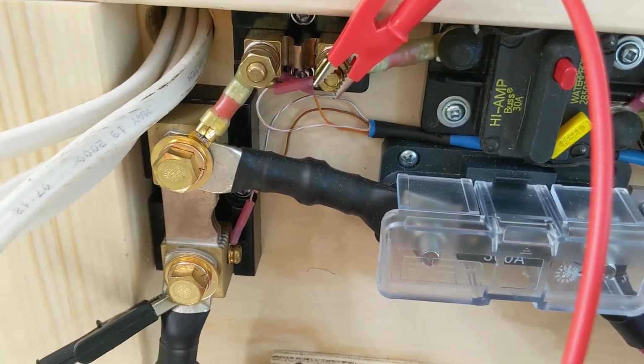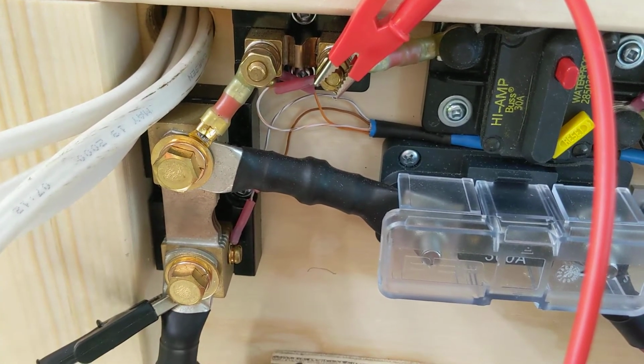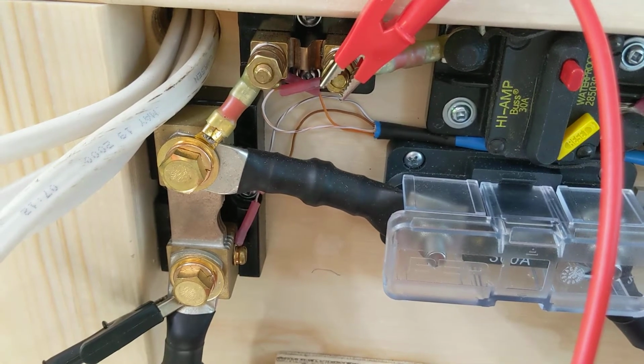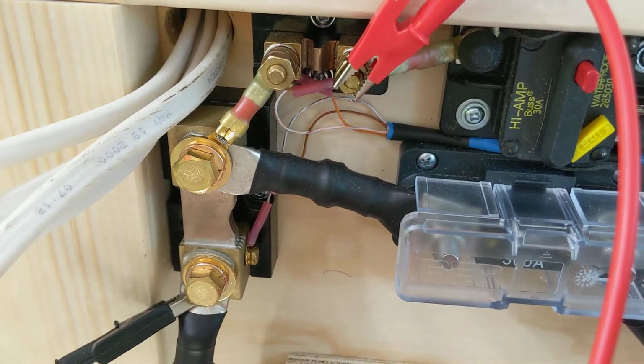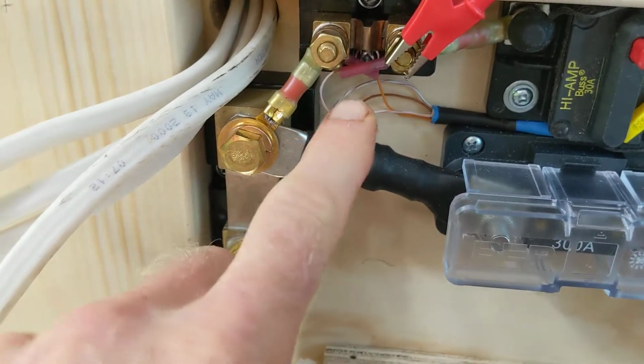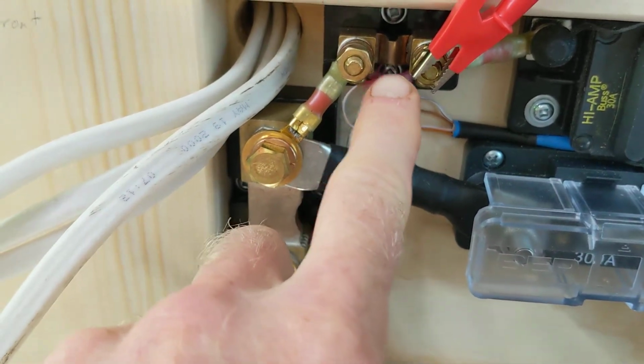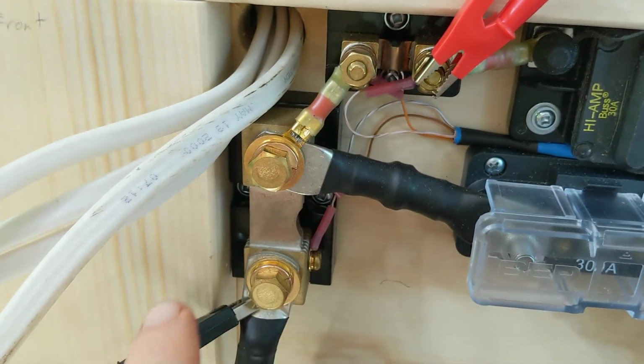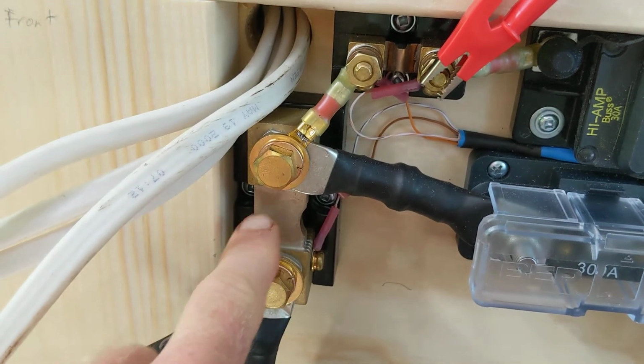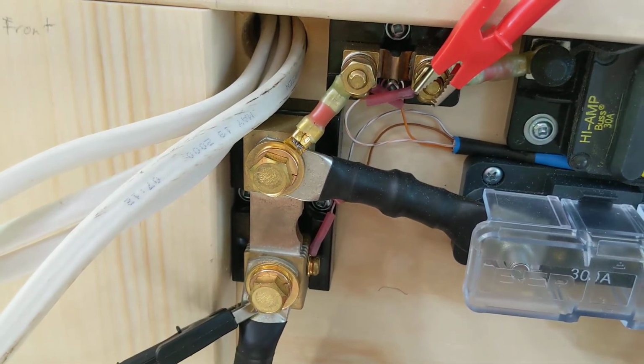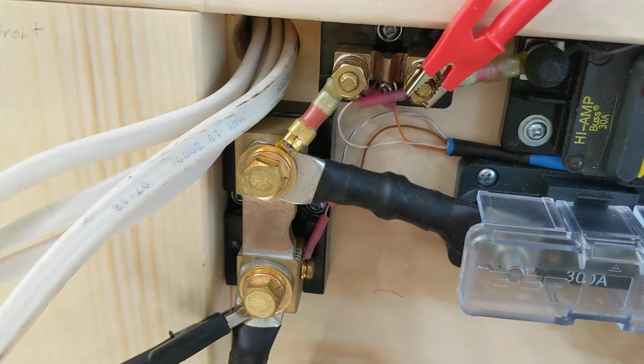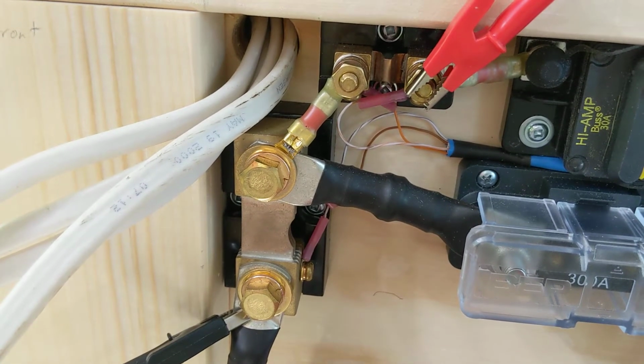I'd just like to document some of the issues I've been having with calibrating the Electrodacus SBMS for my shunts. This is a 50 amp 100 millivolt shunt for the solar panels, and this is a 300 amp 100 millivolt shunt for the battery. Both are supposed to have an accuracy of 0.25%.